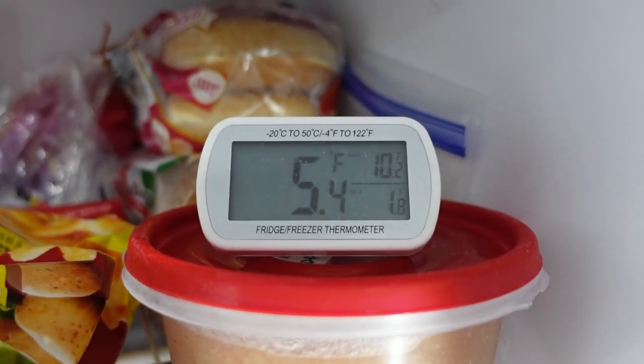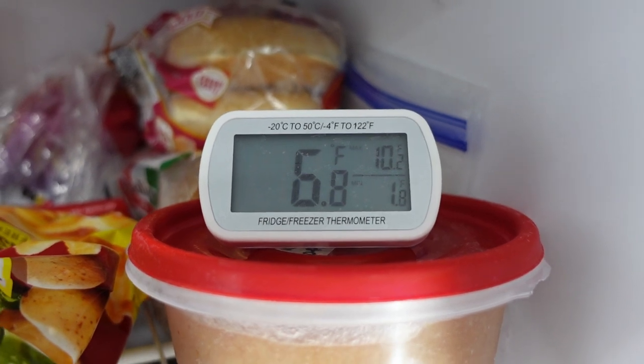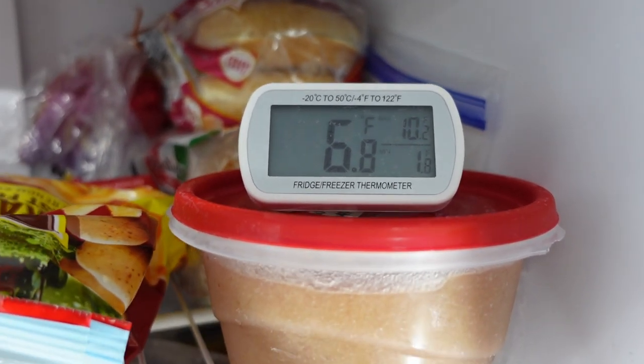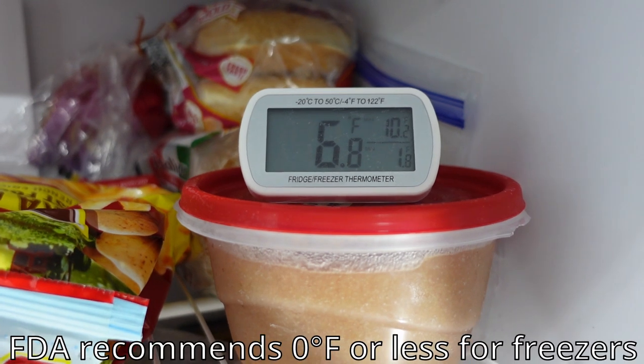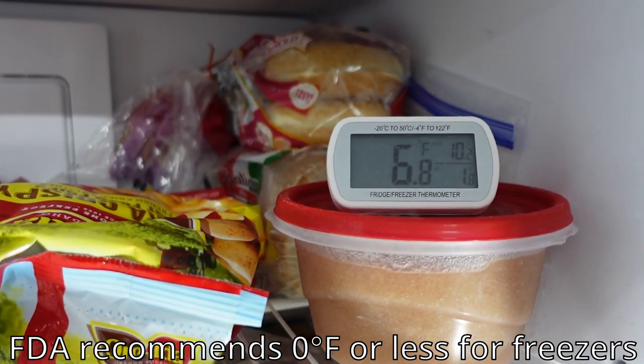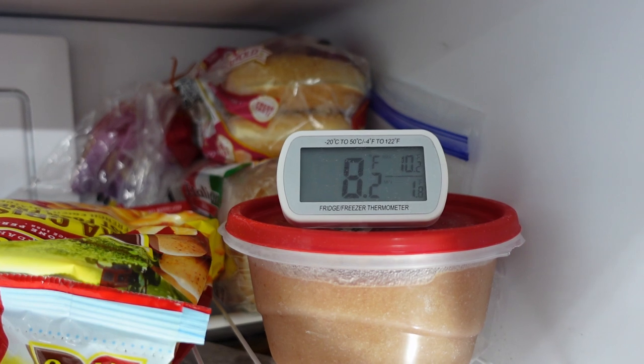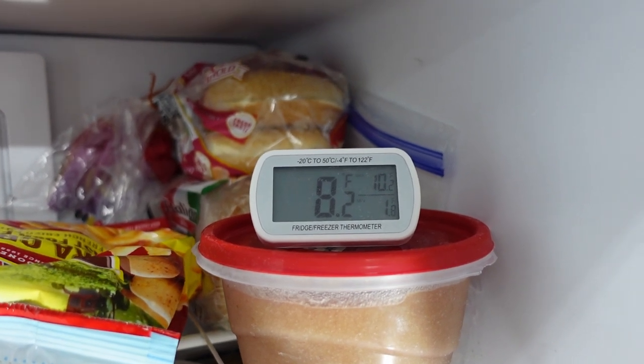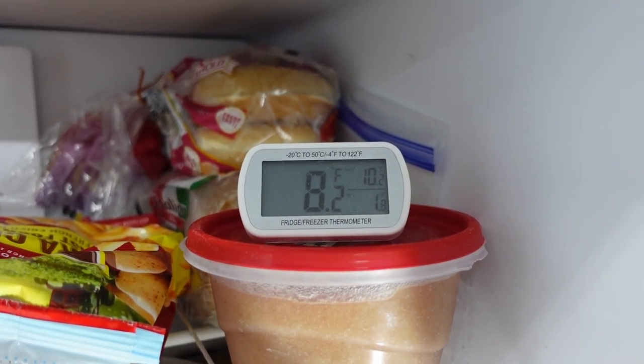All right. So after about 24 hours, looking at about 10 degrees max and about one degree minimum. Obviously I got the door open now, so it's floating around a little bit, but that's about right. I got to adjust the temperature a little bit to make it a little bit colder, but otherwise it's definitely better than it was, which was about 15 or 20 degrees maximum, only about 10 degrees minimum.